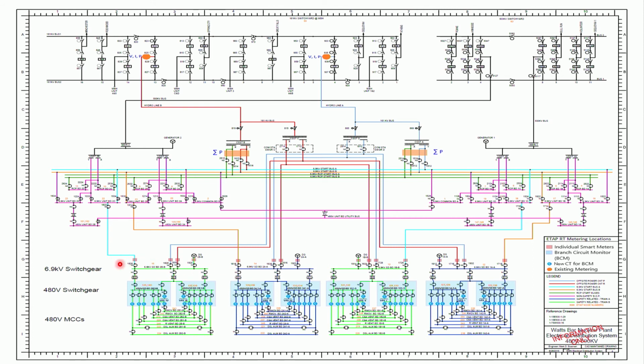These red dots show smart meters that are going to be on the feeders for the 6.9 kV switchgear. The blue areas are branch circuit monitors that we're going to place on the outgoing feeders of the 480 volt switchgear. That's not too many sensors—only 32 sensors in all have to be installed.